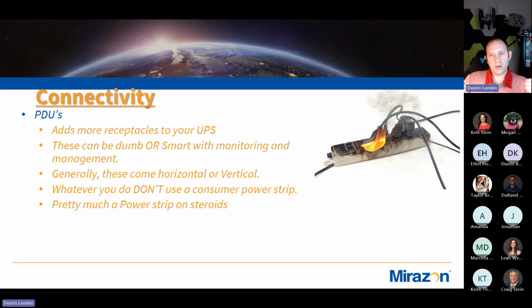The big thing to note is that PDUs are built for server racks, built for that high power draw. Do not use the cheap ones you can get at Best Buy or Walmart, they're not rated for this. In almost every data center we go into, the SMB market, there's a couple of these on the floor with random things plugged into them. These are not built the same—they have different internals, smaller cables. They go bad, they can catch fire, they short out. Please do not use these.